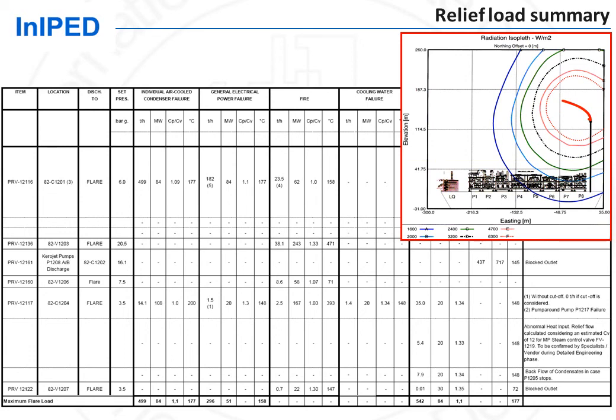Another summary that is produced by process is the relief load summary. It is an inventory of all possible scenarios of relief of gas to the flare. Possible scenarios include emergency shutdown and depressurization of the plant, as well as general electrical power failure, cooling water failure, fire, and other scenarios. The maximum flare load for any scenario gives the sizing of the flare system and allows to size the flare header, flare knockout drum, flare stack, and flare tip. Indeed, the height of the flare is determined so that the level of radiation where personnel could be present is within a safe limit.